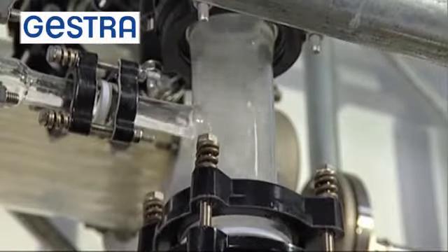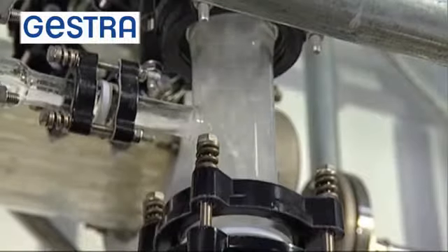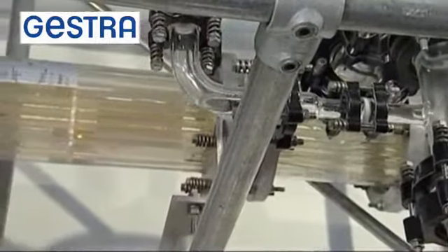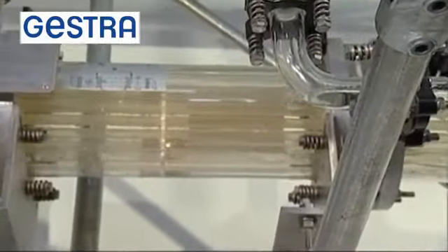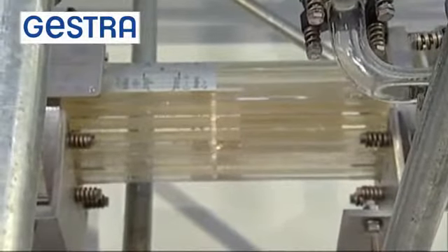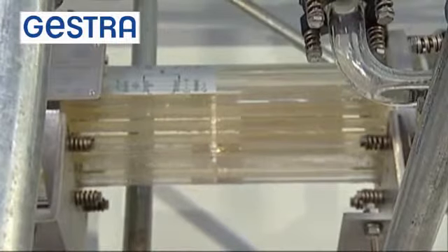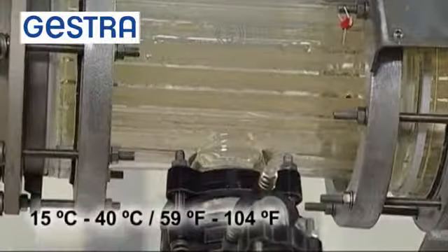Condensate drops can be seen. These are either entrained, in suspension, or flowing back into the steam generator. The saturated steam flows into the heat exchanger. In the heat exchanger, the tubes are charged with a cold medium, water in our model heat exchanger, which is then warmed up from about 15 to 40 degrees centigrade.